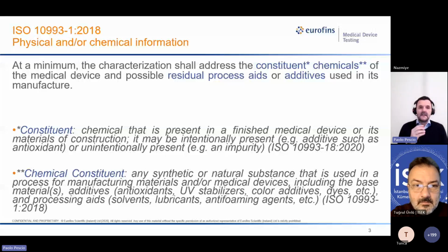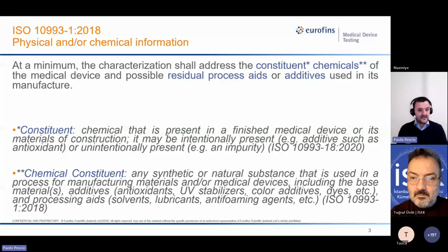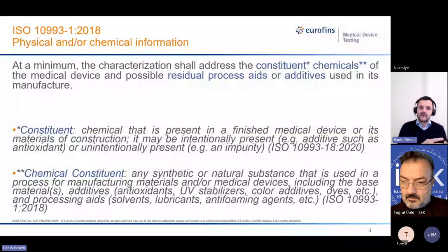And we have two definitions of constituent, or at least I have to say we have three. Let's start with the first two definitions. One definition, coming from 10993-1, says that a constituent is any synthetic or natural substance that is used in a process for manufacturing materials or medical devices, including the base materials, additives such as antioxidant, UV stabilizer, color additives, dye, and so on, and processing aids. So this is the definition from part one with a clear focus on what is intentionally added to the medical device. It's a list of raw materials plus additives used during the manufacturing process.